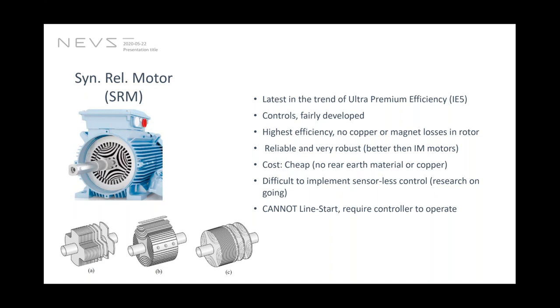The only thing I would mention in the synchronous reluctance machine is the stress that applies on the narrow ridges at the surface of the rotor. Those are the places where the stress during the high speed rotation might cause some issues. But other than that, if that issue has been addressed, it's a very reliable and robust machine.